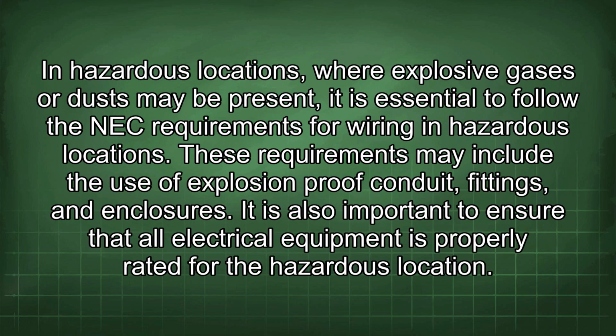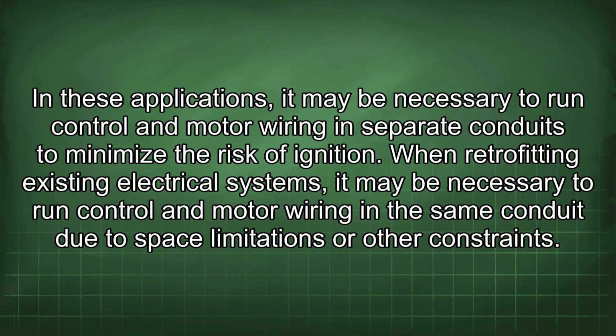In hazardous locations, where explosive gases or dust may be present, it is essential to follow the NEC requirements for wiring in hazardous locations. These requirements may include the use of explosion-proof conduit, fittings, and enclosures. It is also important to ensure that all electrical equipment is properly rated for the hazardous location. In these applications, it may be necessary to run control and motor wiring in separate conduits to minimize the risk of ignition.